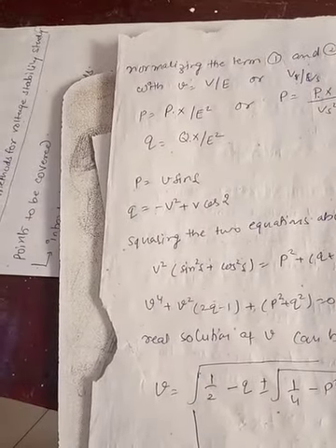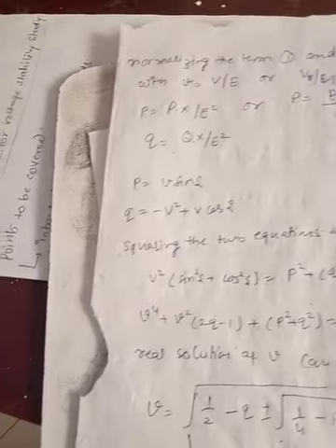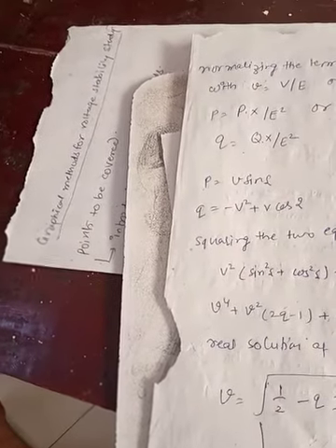So here is the curve between V, Q and P. A plot of V on the PQV plane was shown previously in the video. Corresponding to each point of P and Q, there will be two solutions for the voltage. One is a high voltage or stable solution, and the second is a low voltage and unstable solution.